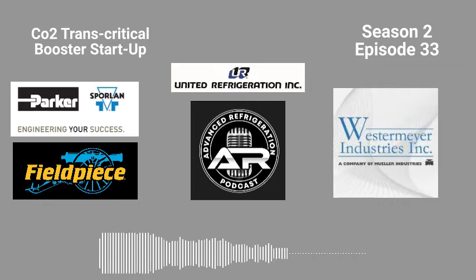Go ahead. How's your charging though? You said before you started feeding the medium temp cases, you were just letting the compressors run on their own, because basically on a transcritical rack, the medium stage should be able to run independently, correct? Yeah, it'll pull off the top of the flash tank. So like I said, you're going to start dumping into the flash tank as much as you can get in there, and then you're going to come to a point where you're going to start equalizing out tanks, and that's just a waste of liquid.